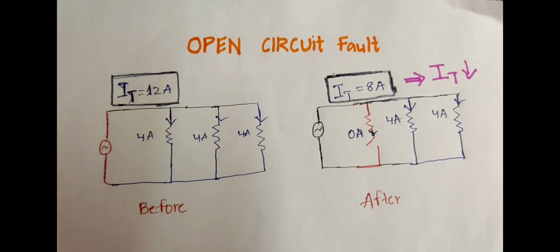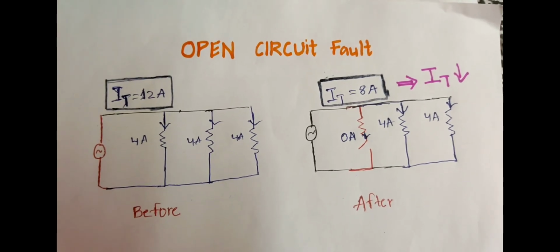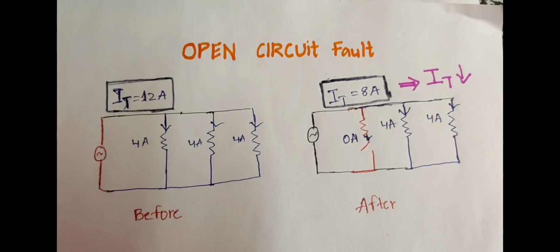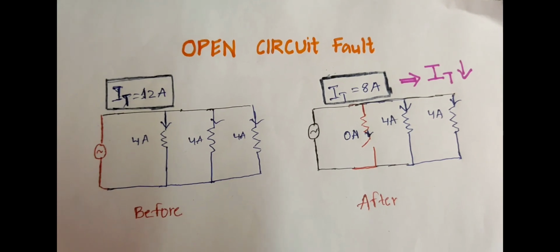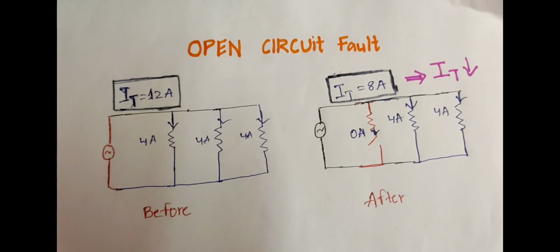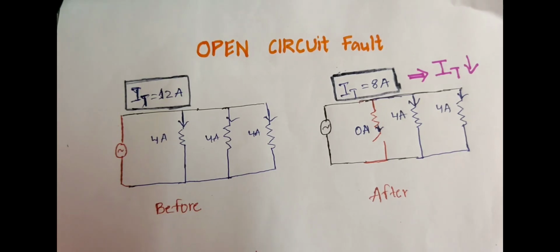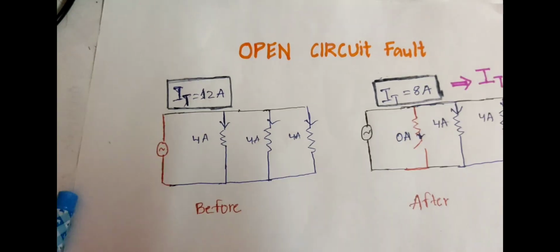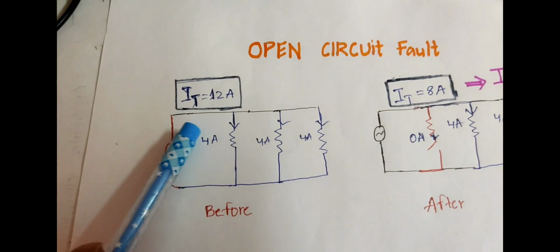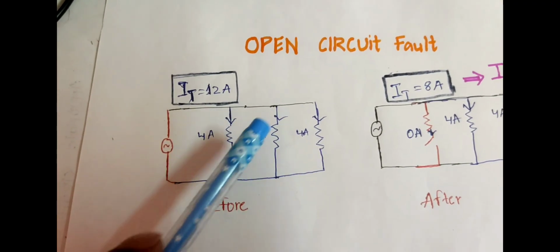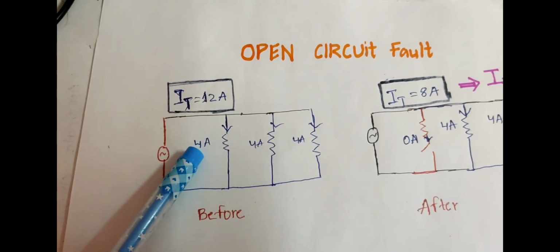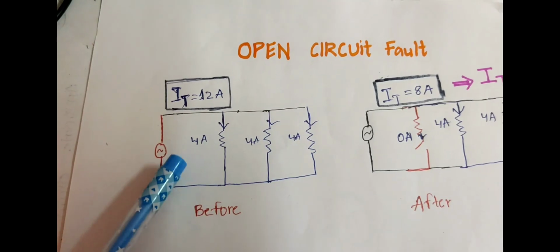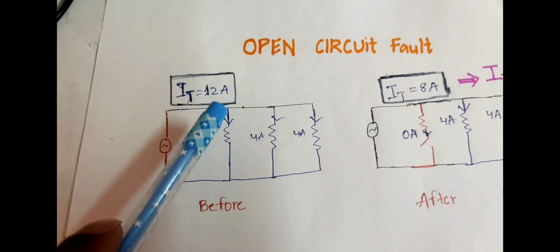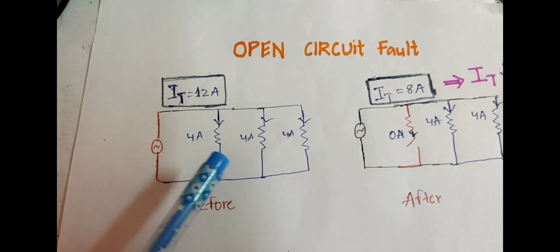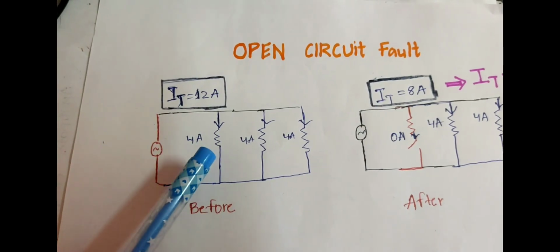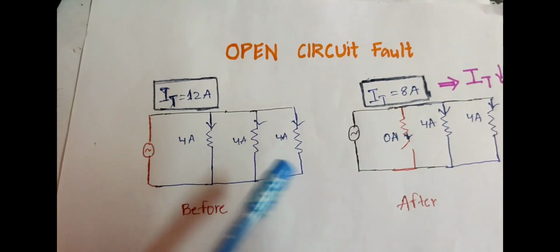What happens at the open circuit fault? Let's take an example circuit, and see how the load current changes after the open circuit fault and how it leads to an increase in the frequency of the system. Let's consider this is a generator and this is a bus bar, and these are the three transmission lines with load currents of 4 amps, 4 amps, 4 amps, and the total load current drawn from the generator will be 12 amps.